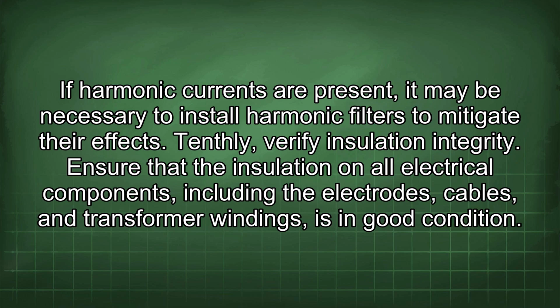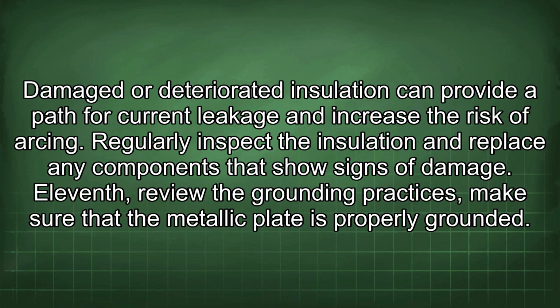Tenthly, verify insulation integrity. Ensure that the insulation on all electrical components, including the electrodes, cables, and transformer windings, is in good condition. Damaged or deteriorated insulation can provide a path for current leakage and increase the risk of arcing. Regularly inspect the insulation and replace any components that show signs of damage.